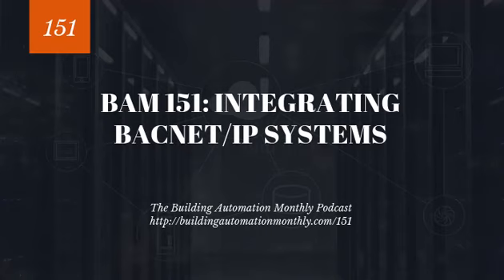So with our protocol specifics, we need to understand our protocols, hence why I said you all should enroll in the BAS Protocol Fundamentals course, or the BAS Protocol Bootcamp course, because it's going to teach you all of this. But with that being said, at the top layer, especially because we're using BACnet IP, if we are connecting between subnets, then we need to account for our BBMD. Our BBMD is going to take those Who-Is, I-Am messages that are broadcasts, and forward them to additional BACnet networks.